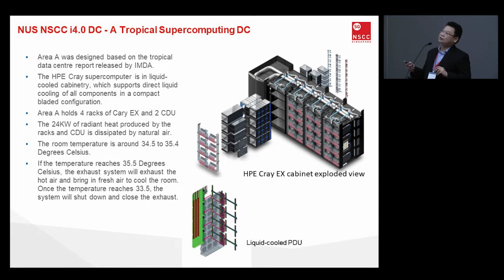As I mentioned, we are getting rid of the 24 kilowatts of radiant heat by natural air. All right, so the room temperature is also unique as with the Tropical Data Center report. Since you don't have aircon, the room temperature is expected to be high. But however, our room temperature is running at about 34.5 to 35.4 degrees Celsius. This is how hot it is in the room. Okay, it is purpose-built this way. All right, so one of the reasons why we run it so hot is firstly, we do not want to expend additional energy to cool the room. It's not required. It's a waste of energy. The system is designed to run hot.